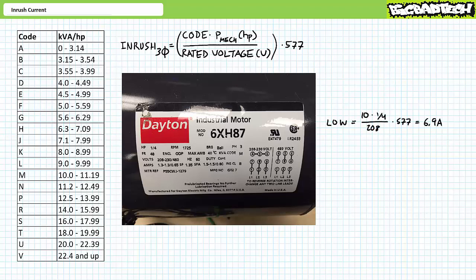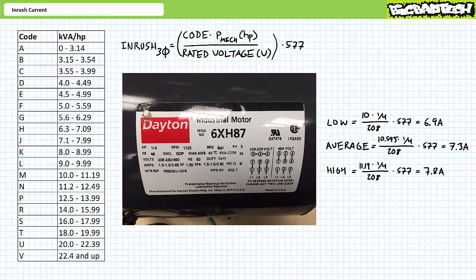However, this rough estimate isn't exactly accurate. At the low end, M equals 10, yielding a lower bound of roughly 6.9 amps. In the middle, M equals roughly 10.6, resulting in a middle estimate of roughly 7.3 amps. At the upper end, M equals roughly 11.2, resulting in an upper bound of roughly 7.8 amps. We might therefore expect this motor to experience an inrush of roughly 6.9 to 7.8 amps — a far more precise estimate than the six times rated current shortcut, though it illustrates the shortcut isn't that bad for this particular system.